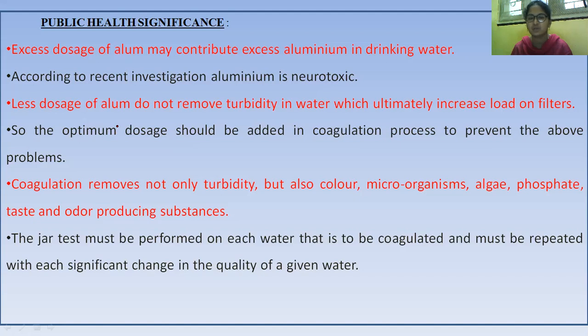Coagulant removes not only turbidity but also color, microorganisms, algae, and taste and odor producing substances. And also the jar test must be performed on each water that is to be coagulated and must be repeated with each significant change in the quality of a given water.